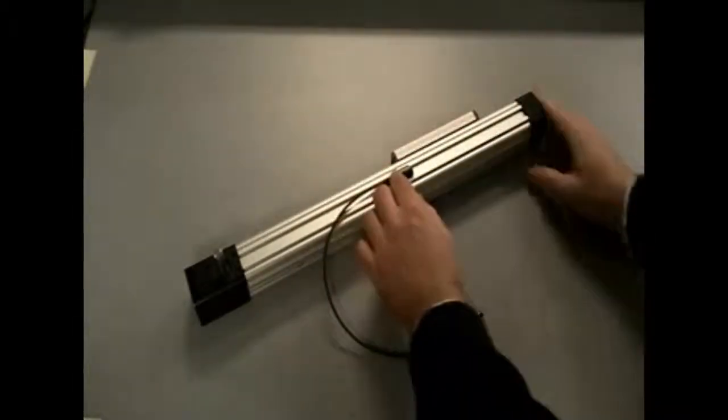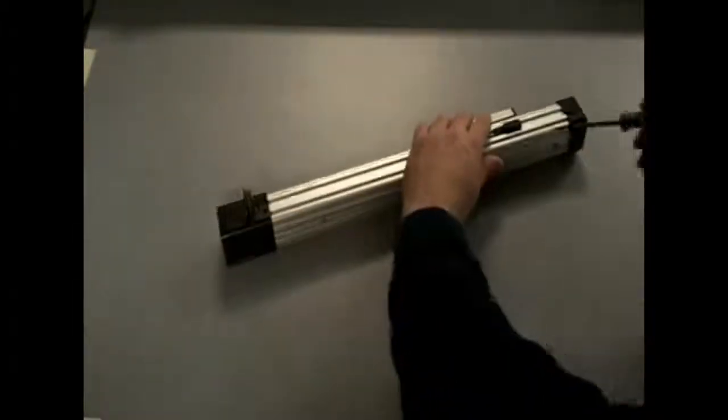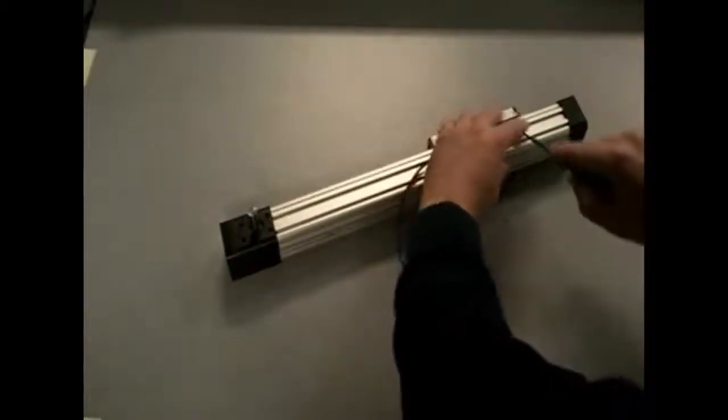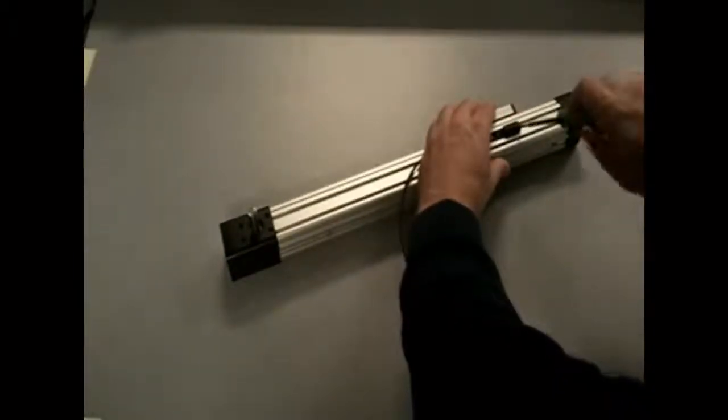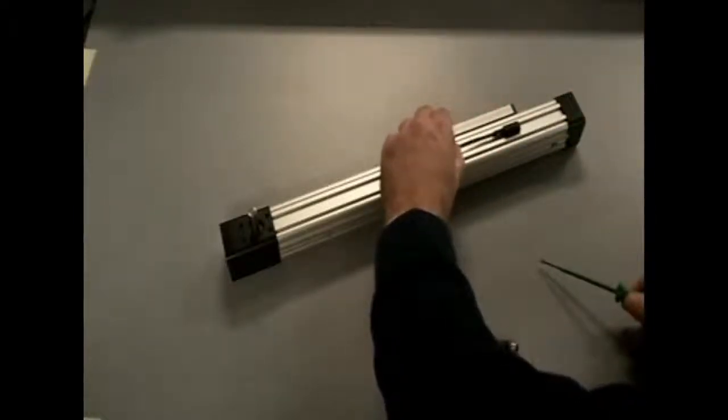Position the sensor into its desired location over the length of the actuator. Using a small flathead screwdriver, apply 1.8 inch-pounds torque to the screw within the sensor. This will secure the sensor into its desired location.